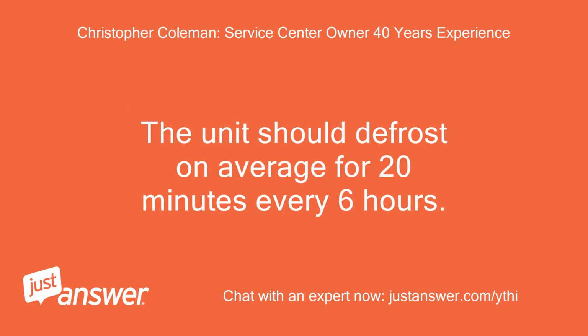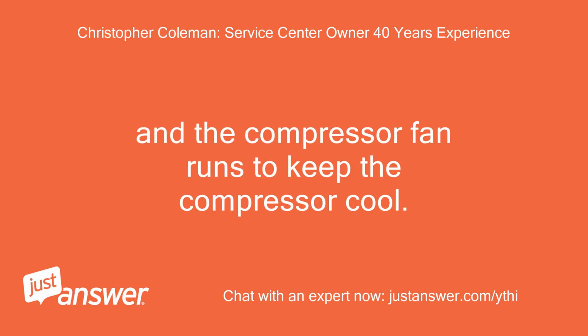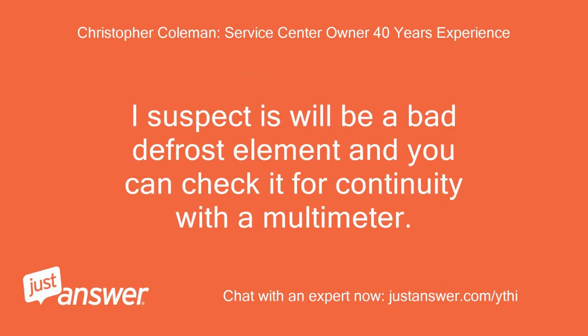The unit should defrost on average for 20 minutes every 6 hours. Make sure the compressor is free of dust, grease, spider webs, etc. And the compressor fan runs to keep the compressor cool. When you take the freezer panel out to expose the fins, make sure to check the drain as well to see if the defroster is working and the ice melt is stuck, causing it to become a solid ice block when the compressor kicks back on after the defrost. I suspect it will be a bad defrost element, and you can check it for continuity with a multimeter.